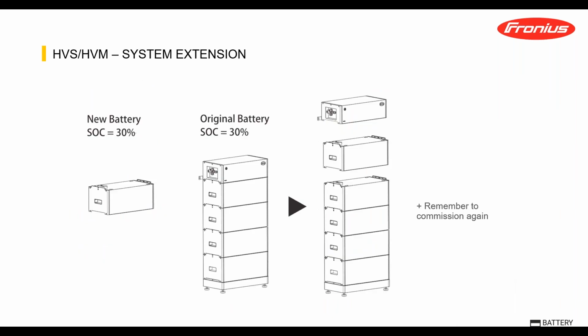You have about 16 error codes you can read on the battery LED. For normal installations this isn't necessary, but if you're expanding the system later, note that batteries come from the factory at 30% state of charge. If you add a new battery in series, the same current goes through all batteries, so if the state of charge differs a lot, it will be difficult for them to balance later. To avoid problems and capacity losses, make sure that when adding a battery to an existing tower, the system's state of charge is at 30%. Wait until that's the case for the smoothest extension.